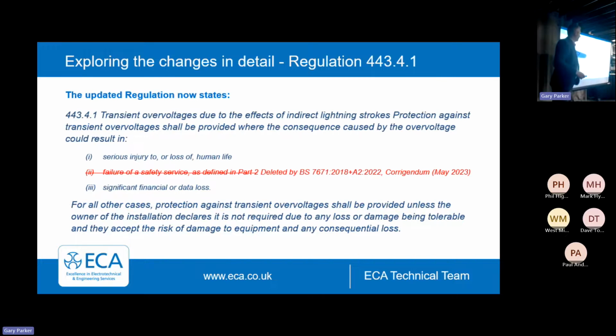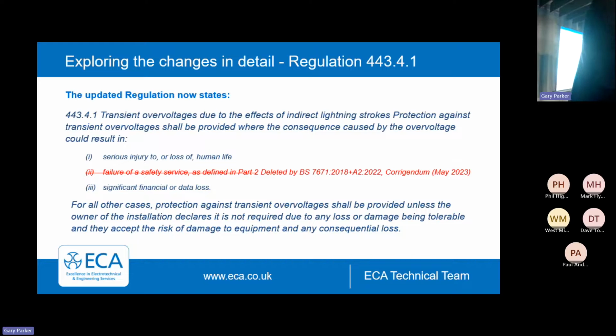So that one was deleted. Doesn't mean you don't have to consider it - you can do, of course you can. And you probably want to fit things like a fire alarm panel. If you've got a big mains panel, yeah, you might want to fit an SPD, but not for small stuff. Really isn't necessary. So that has been removed in the corrigendum.